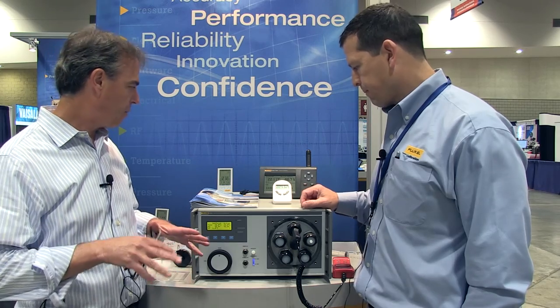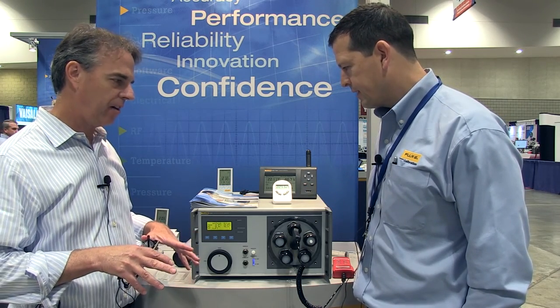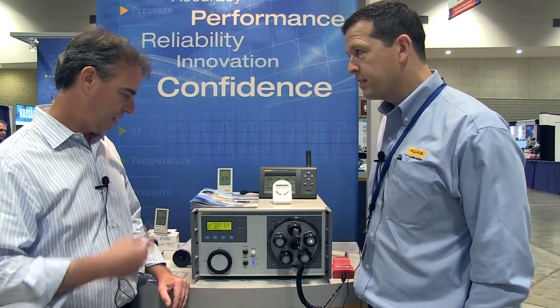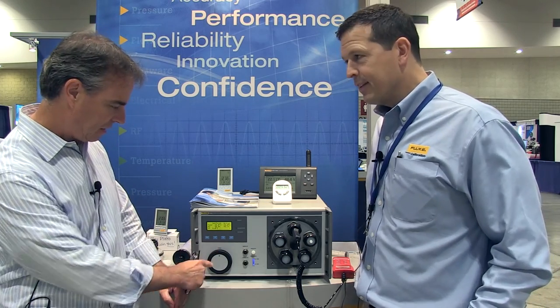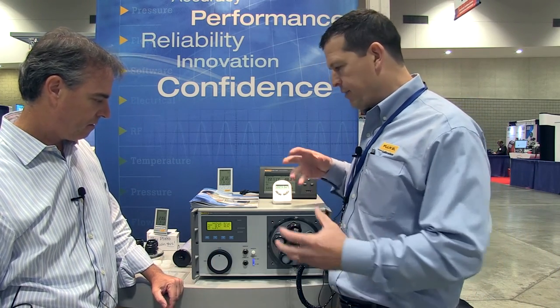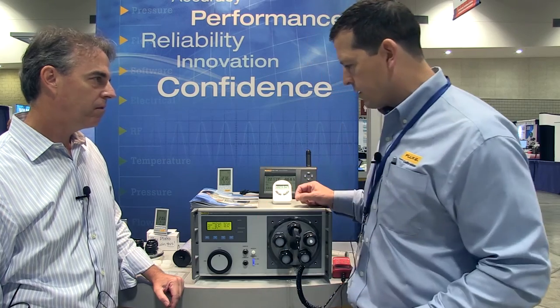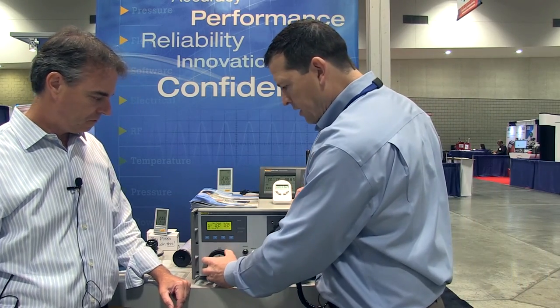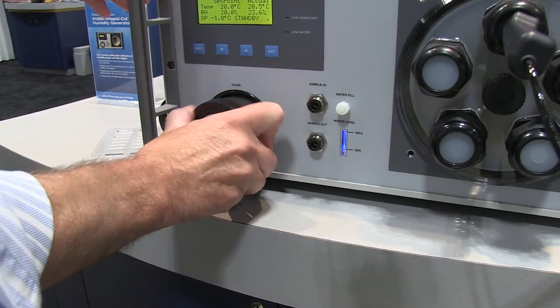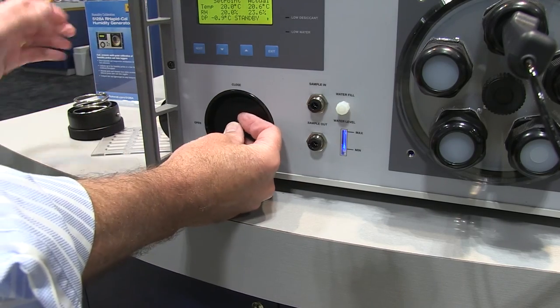So somewhere in here, there must be some kind of desiccant dryer to give you the dry air stream. Exactly. Where do you access that? Is that what this is? Yeah, a lot of units you see would have an external desiccant, kind of on the back or side of the unit. In this unit, it's right here on the front. You access it by turning this knob and pulling the desiccant out.